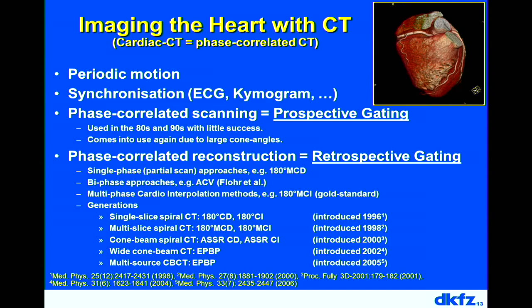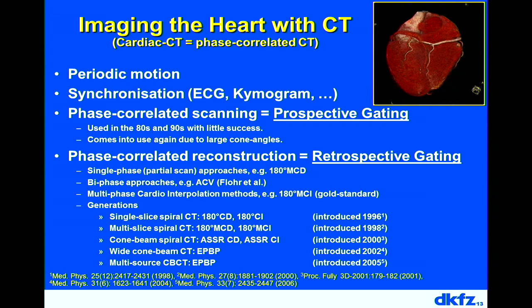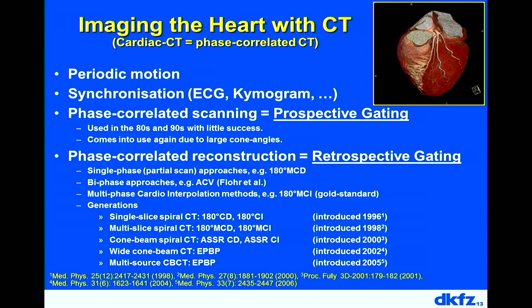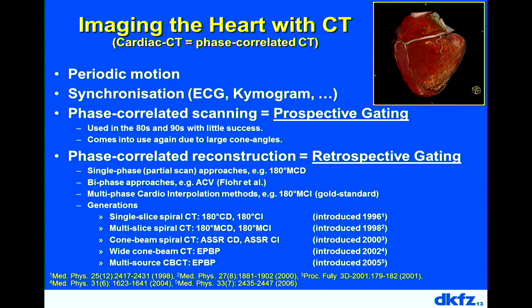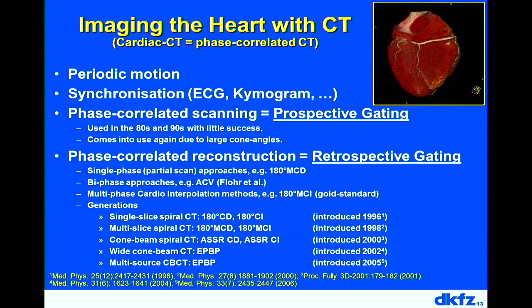Prospective gating was used in the 1980s and 90s with limited success; retrospective gating made a big success in cardiac CT, and today both options are used. Prospective gating is somewhat less robust: for patients with irregular heart rates or extra systoles that show up in the ECG but not as motion, a prospectively gated scan might be done at the wrong time position. For patients with irregular heartbeats, retrospective gating is preferred.